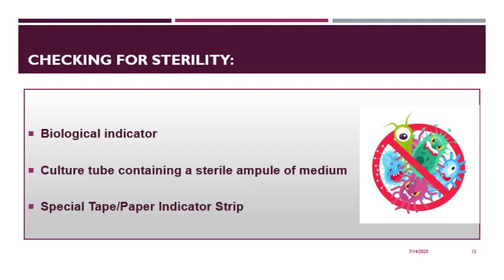stearothermophilus. After autoclaving, the ampule is aseptically broken and the culture incubated for several days. If the test bacterium does not grow in the medium, the sterilization run has been successful. And the second one is the special tape or the paper indicator strip.